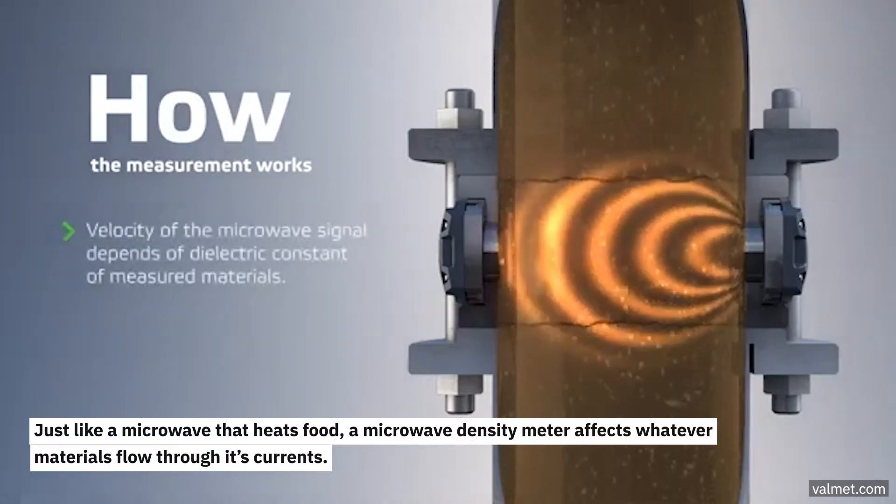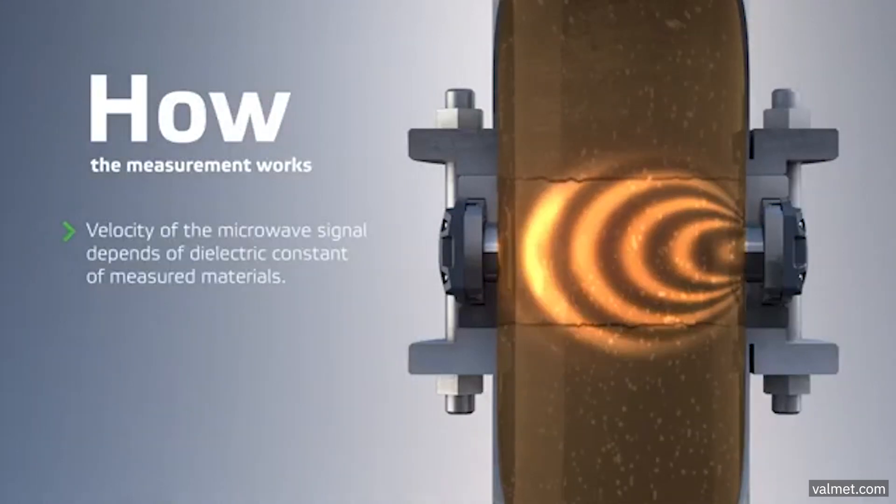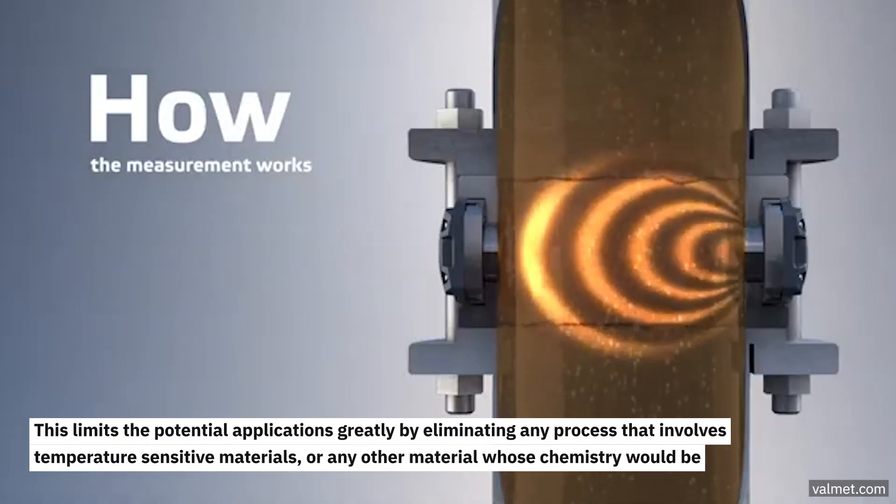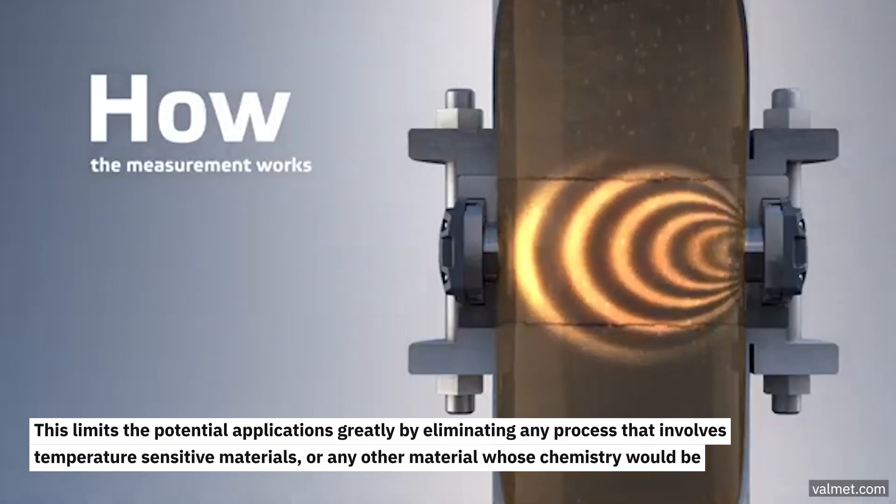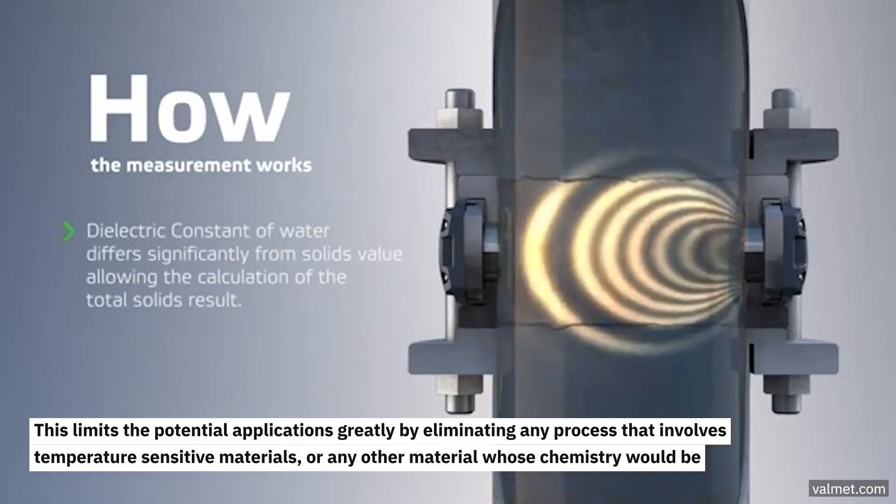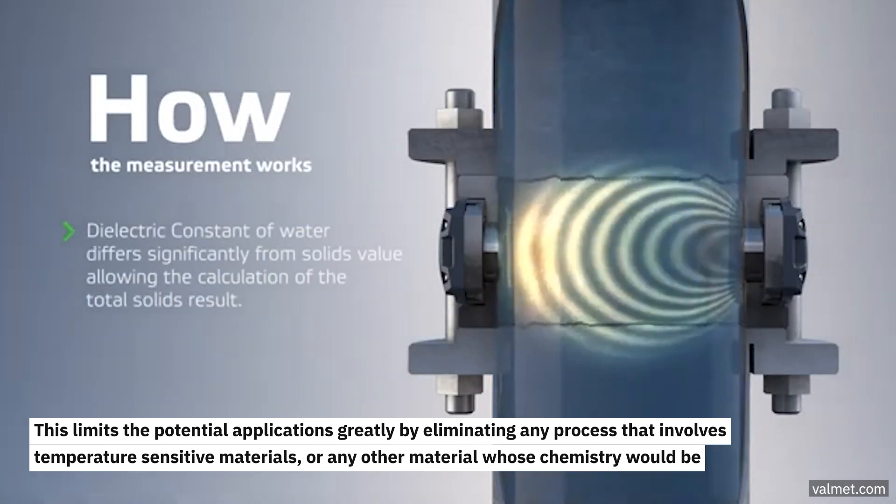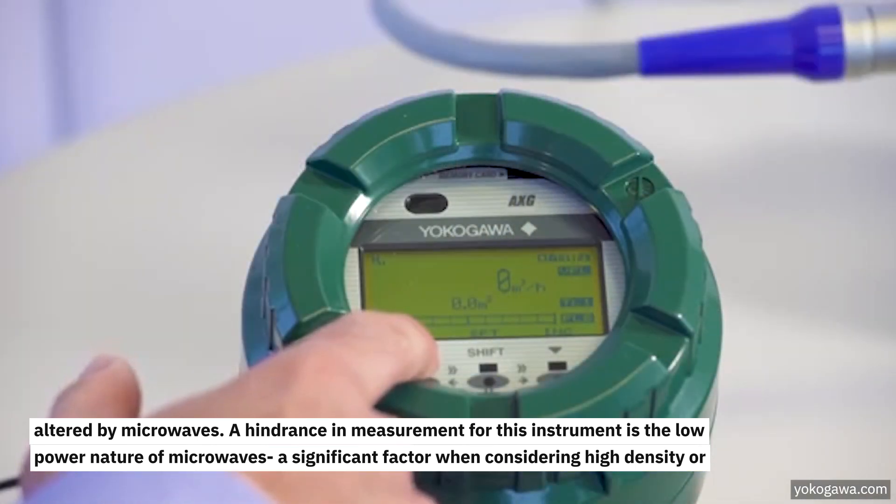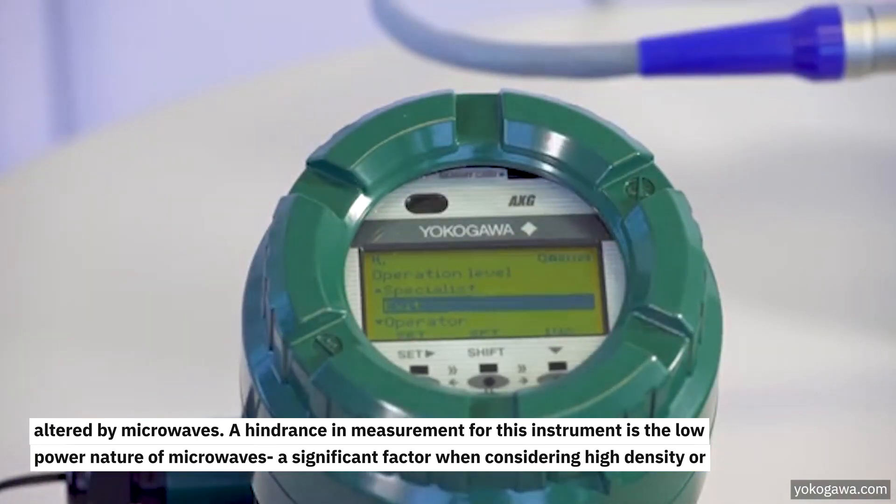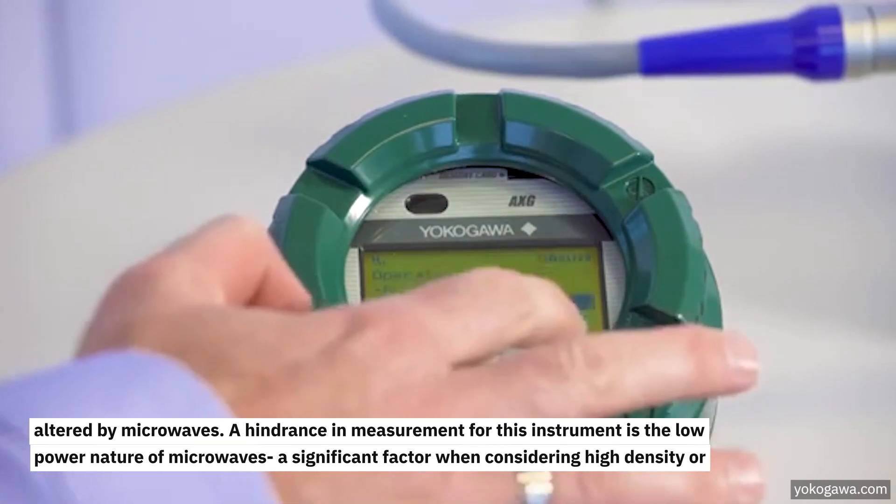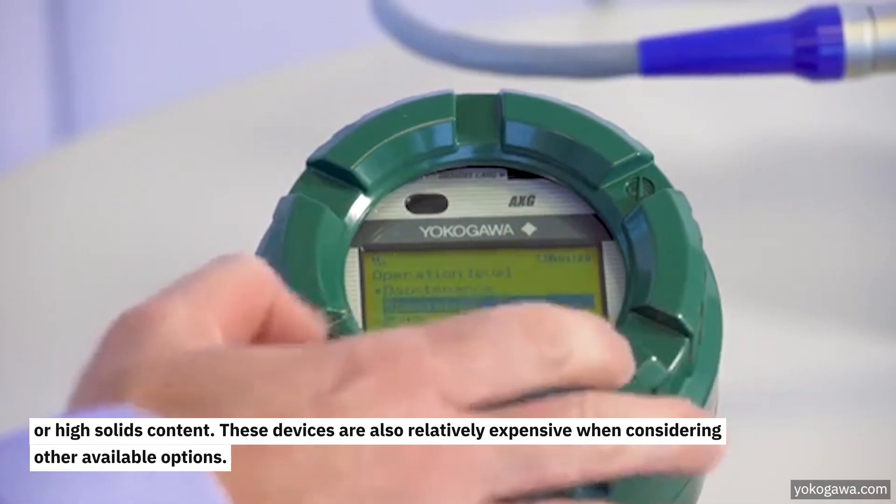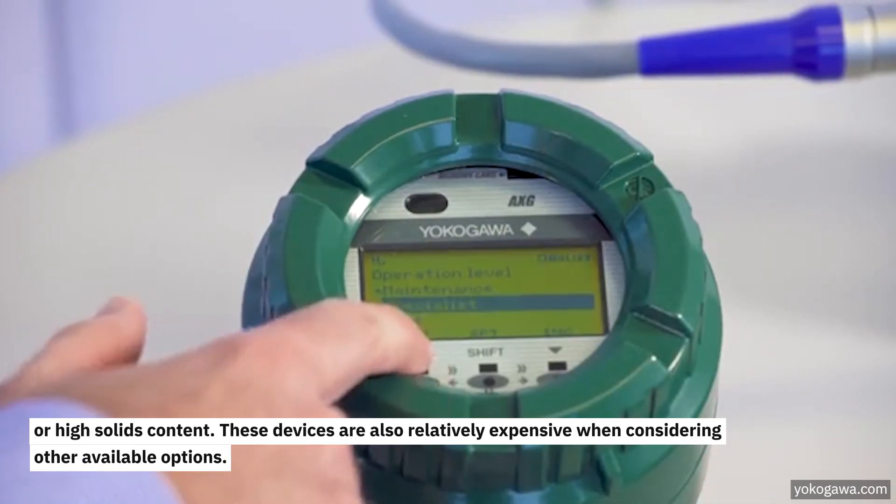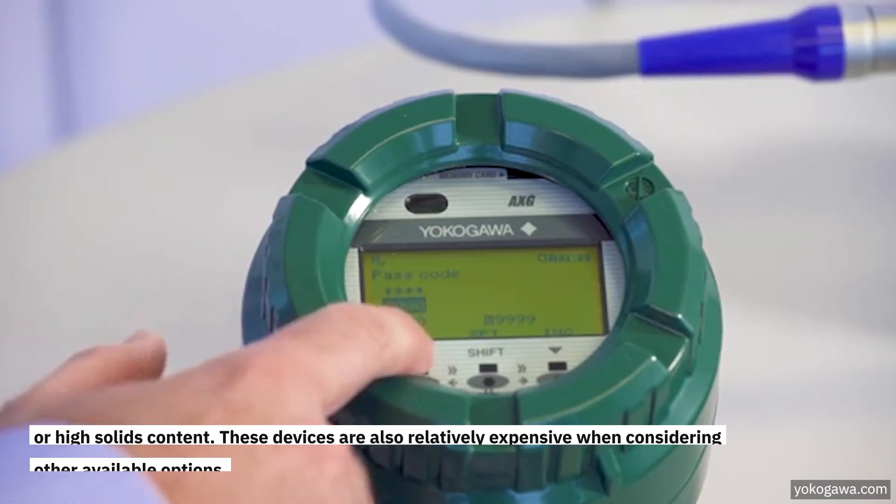Just like a microwave that heats food, a microwave density meter affects whatever materials flow through its currents. This limits the potential applications greatly by eliminating any process that involves temperature-sensitive materials or any other material whose chemistry would be altered by microwaves. A hindrance in measurement for this instrument is the low power nature of microwaves, a significant factor when considering high density or high solids content. These devices are also relatively expensive when considering other available options.